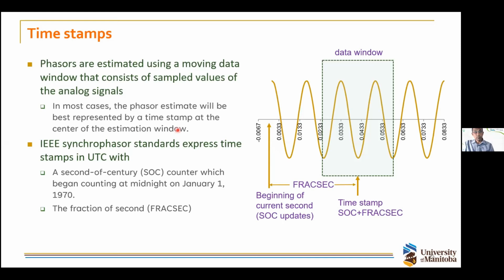Yeah, so in the PMU standards, the accuracy is defined based on whatever it receives at its input, and then you compute the phasors based on that. So with respect to whatever signal you receive at its input, you have to calculate the phasors under that required accuracy. Of course, if your CTs and PTs have errors, that will be reflected in your measurements. If you know the errors, then you can probably compensate for that. But that is some error happening outside the phasor measurement unit.